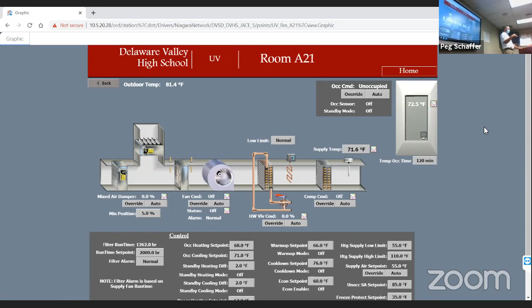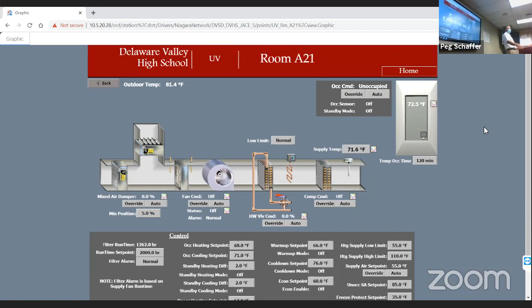We can tell when nobody's in there, so what we do is settle it back for a few minutes. If someone goes to lunch and is back in 20 minutes, we don't want the room to drop by 5 degrees, because they'll come back complaining. So we let it drop by a couple of degrees and stop bringing in that fresh air we have to pay for each time, then turn it back on when somebody walks back into the room. Pretty neat feature.